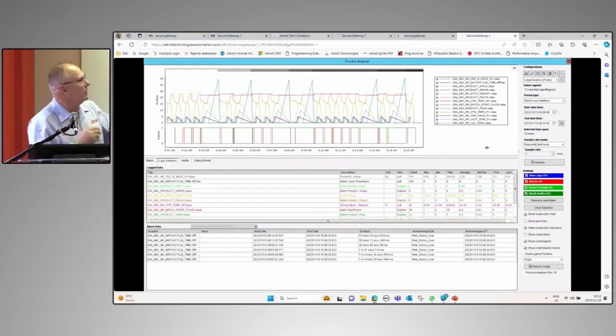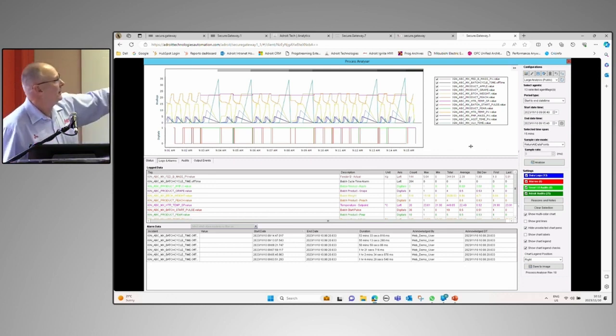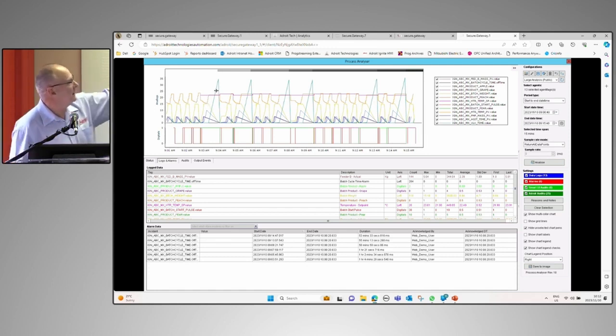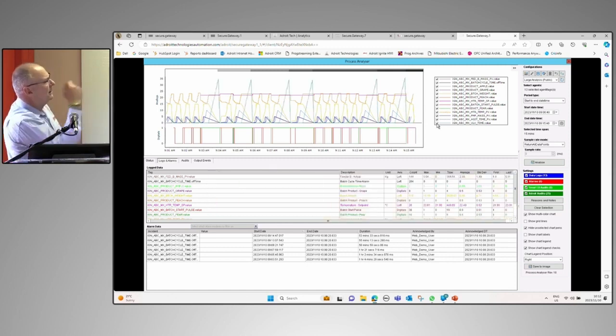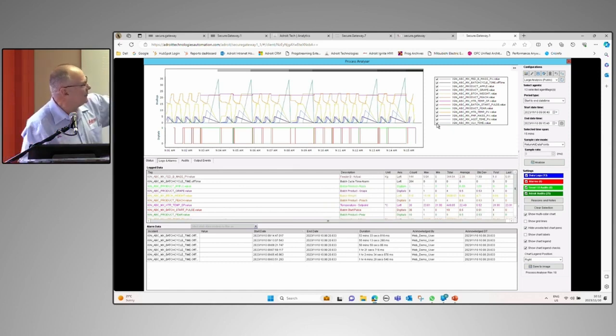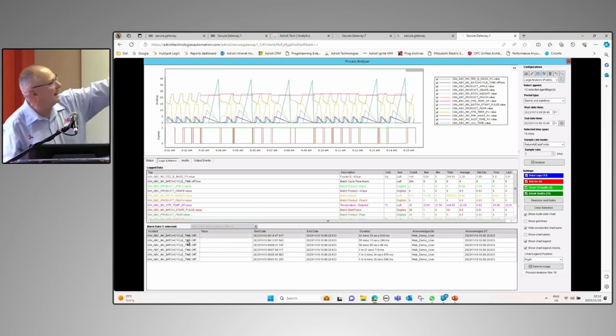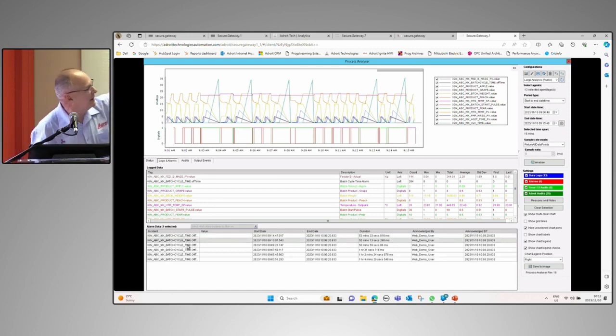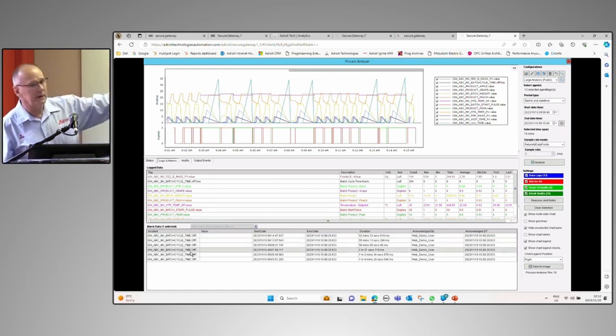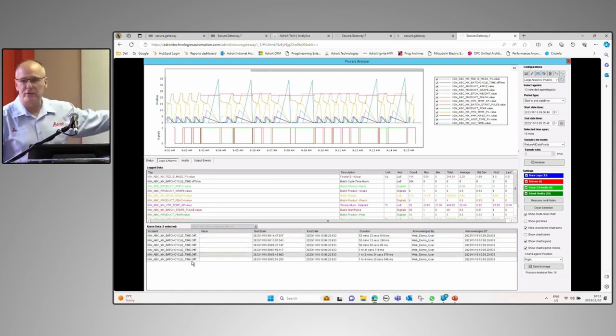So normally you would go to the process trends, and it would be showing you that, what is the spike, John? What is the spiky one? Discharge. Okay, so you can see suddenly the discharge time is going up in spikes. And you wonder, well, what is happening there? You can also see the batch cycle time alarm. You can click on there and it'll highlight where you've got it. You can see it's happened every single time after one of those batches has run.